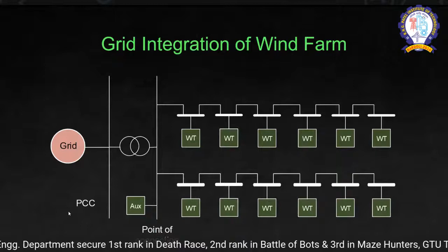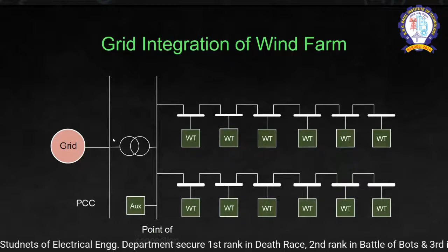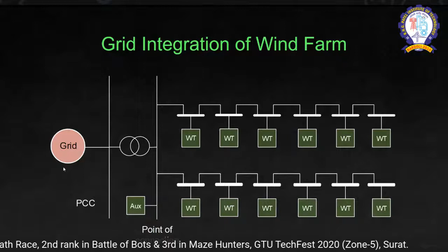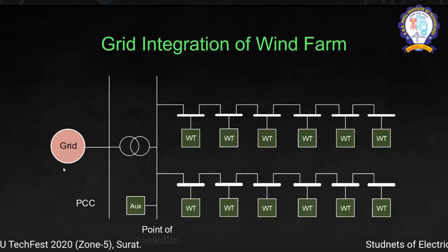In the current state of electrical engineering advancement, we incorporate FACTS devices, or SVC, STATCOM. We need to connect auxiliary active and reactive power mechanisms, particularly reactive power mechanisms, or FACTS devices at the point of connection, where power is controlled, whether active or reactive. Usually we have an active power pumping mechanism to generate higher revenue, but the grid has its own power factor, so we need to produce power at a particular power factor, because the grid does not always operate at unity power factor.